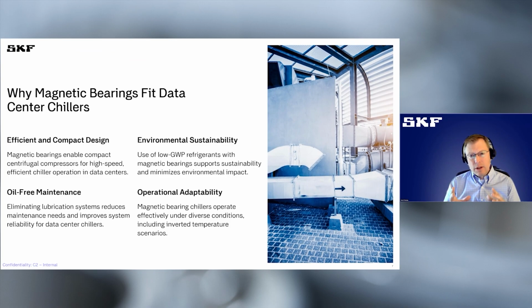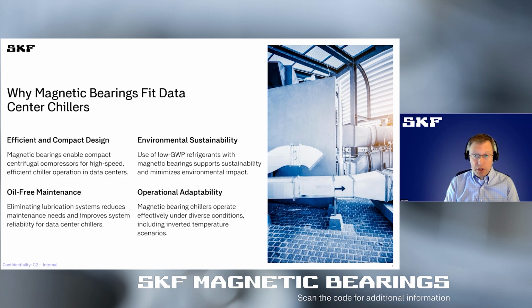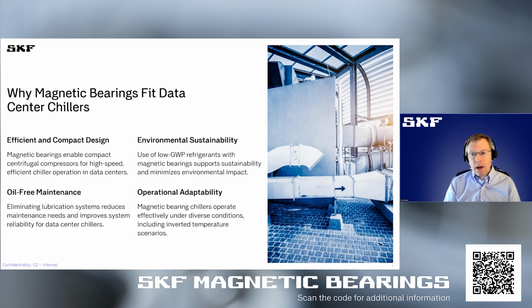The chiller that utilizes SKF magnetic bearings is not only more efficient than other technology on the market, but the chillers themselves can be designed in a more compact and efficient way. Without oil lubrication systems and the associated maintenance, the chiller itself is greatly simplified. And like a juggler, these systems with SKF magnetic bearings are flexible and versatile to handle a wide variety of situations, ready for whatever is thrown at them.